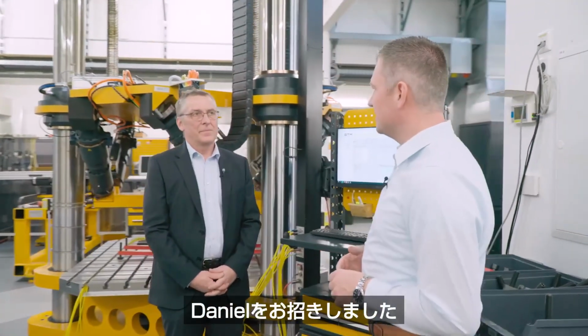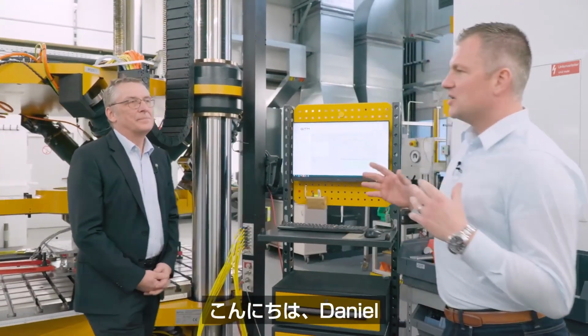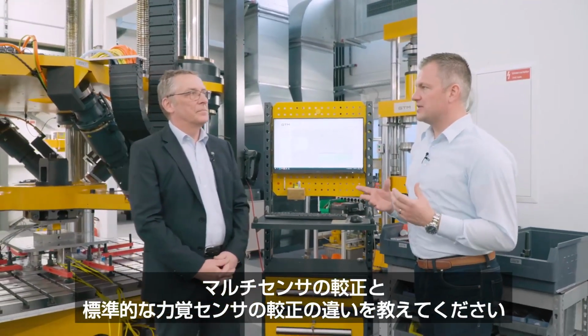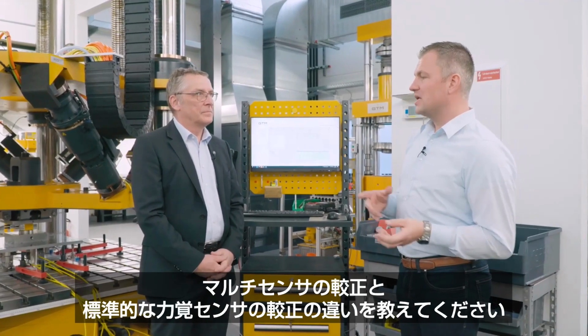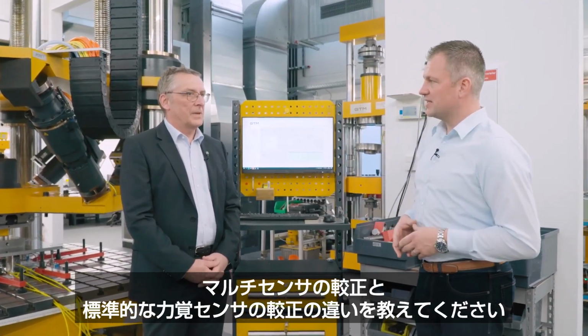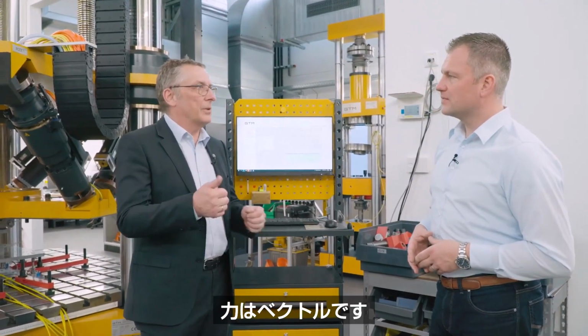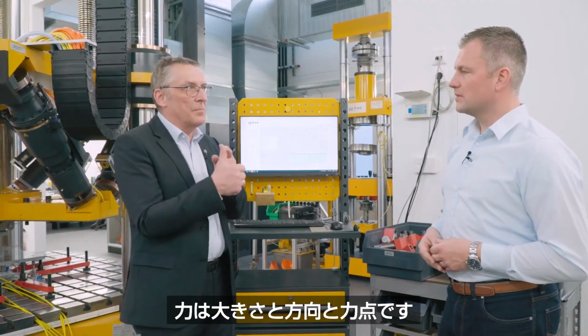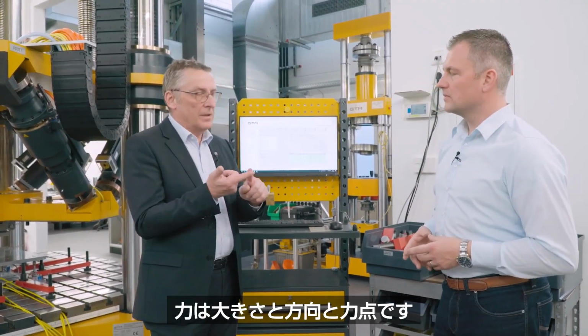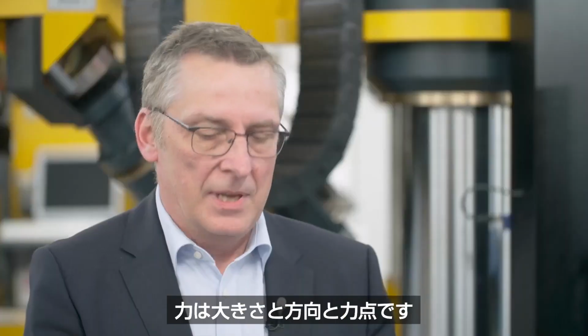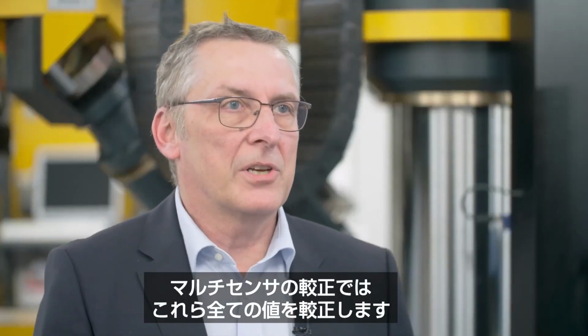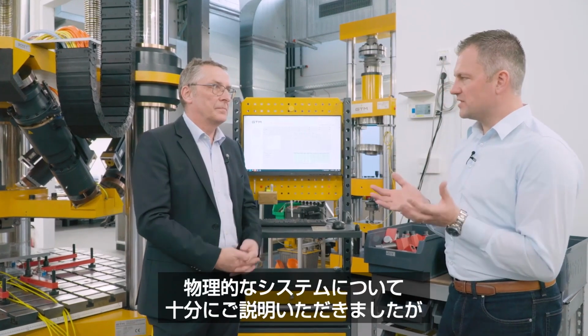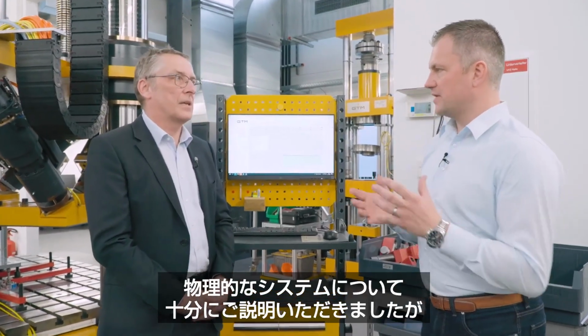With me is Daniel. Hi Daniel. Hello Christian. Could you describe the main difference between multi-component calibration and standard force calibration? Yes, force is a vector, and this force has a magnitude, a direction, and force application points. And in multi-component calibration, we calibrate all these properties. In the classic force calibration, we only calibrate the magnitude. So you fully described the physical system of this machine.